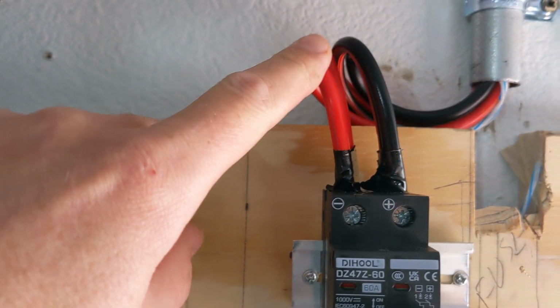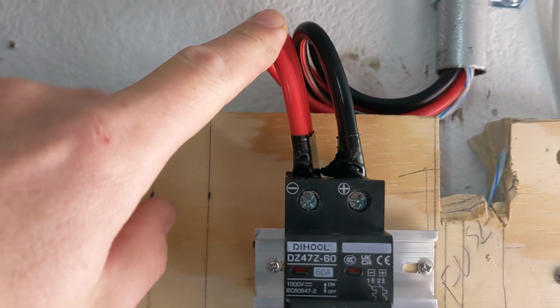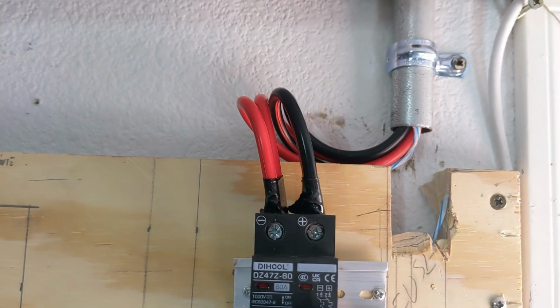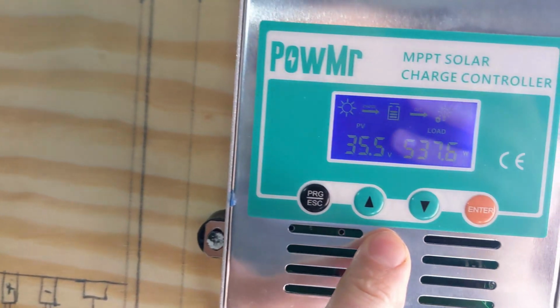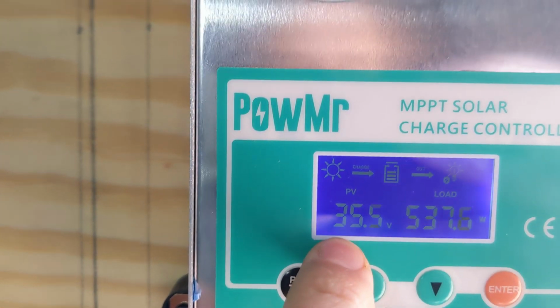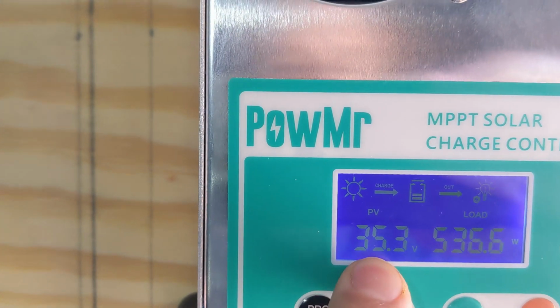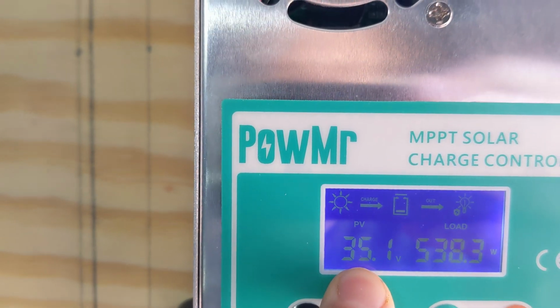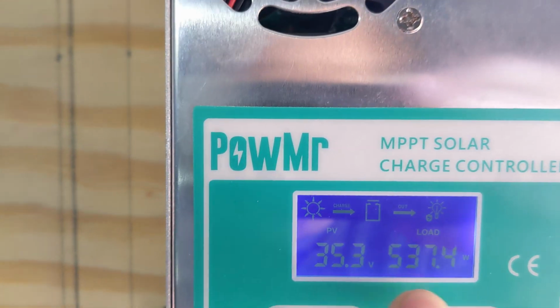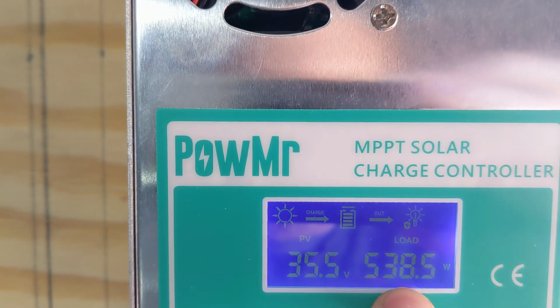Now, if you run thick cables, and I have two 8 gauges coming in here, they could handle 50 amps easy, and there's a short distance to the panels. I've decided that if I run them at 24 volt in MPPT mode at 35, 36, 34, then I get the maximum wattage out of them.